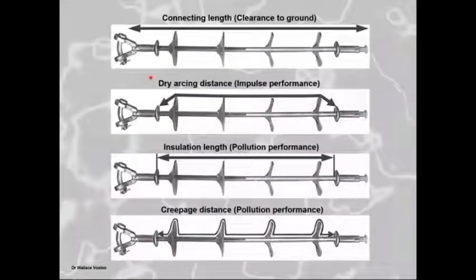Now, the parameters on insulators, the measurements you need to very clearly understand before you can do insulator selection. The first is your connecting length. That is from the hardware where it interacts with the tower to the hardware where it interacts with the conductor bundle and the conductor bundle's yoke and geometry there. That distance from the ball to the Y clevis is your connecting length, and that normally influences your clearance to ground. So that is one parameter.